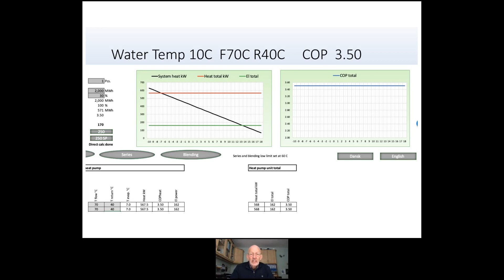If we move on to the next slide, again, we've got everything the same. Here we've got lower operating temperatures, similar delta T. We're now up to 3.25. And to move further on, we've got a really good COP of 3.5. This is because now we've got a flow of 70, a return of 40, a healthy delta T, and a really good COP number. This is possibly the ideal scenario, where we've got flow of 60, return of 40, and a COP of 3.75.